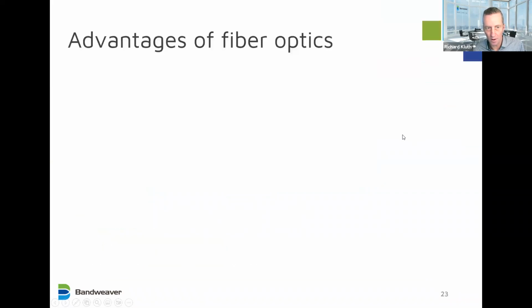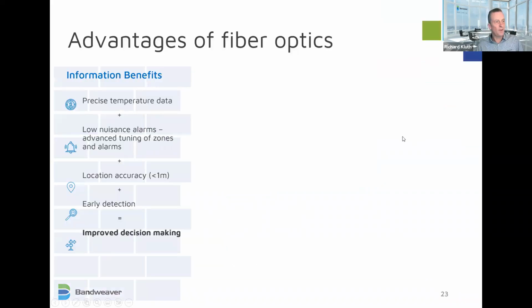So some of the advantages of these systems, we'll divide into three different categories. First, the information benefits: you have precise temperature data, which you can use in many other systems. You have very low nuisance alarms. You can tune the zones to each specific environment. You get location accuracy down to 1 meter, and very early detection with the smart alarms and the rapid measurement time. So getting all this information early allows the user to make much improved decisions.